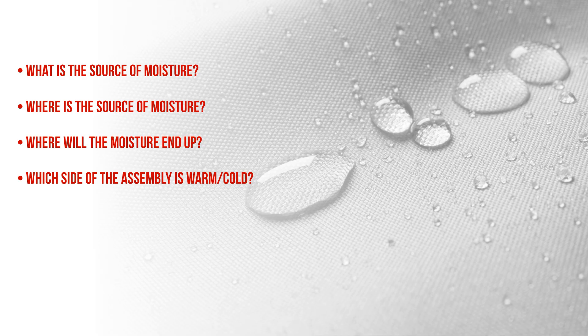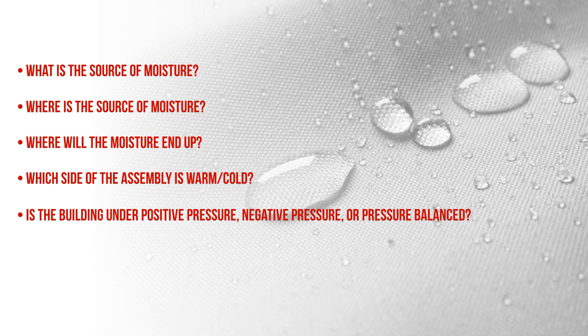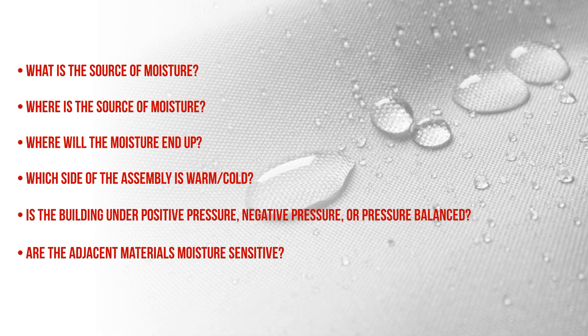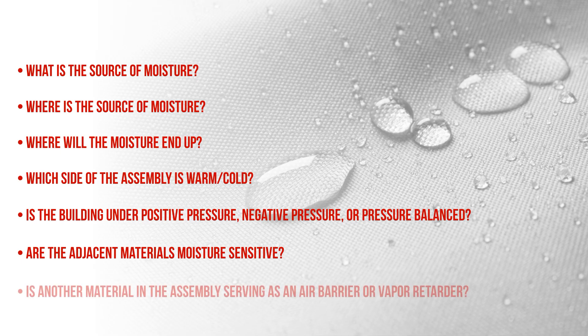This gets even more complicated if moisture is moving in different directions throughout the year. Is the building under positive or negative pressure, or pressure balanced? A building under negative pressure with exhaust-only ventilation will draw air in through leaks from the exterior, while a positively pressurized building pushes air out. Are the adjacent materials moisture sensitive — wood or steel framing, gypsum or wood sheathing? Is another material in the assembly already serving as an air barrier or vapor retarder? This is a big consideration to avoid a double vapor barrier scenario, where moisture trapped in the assembly can't dry out.